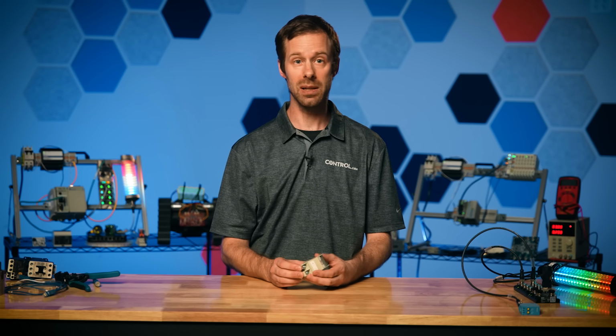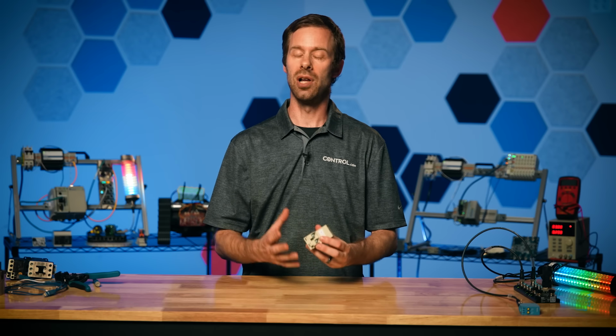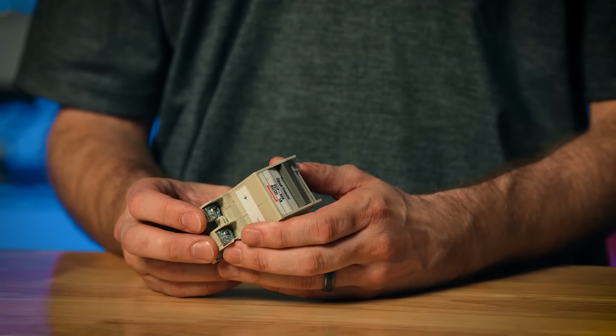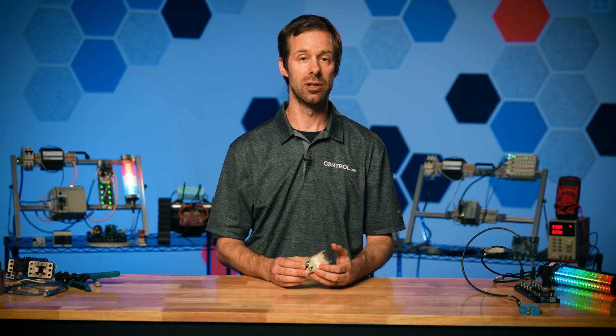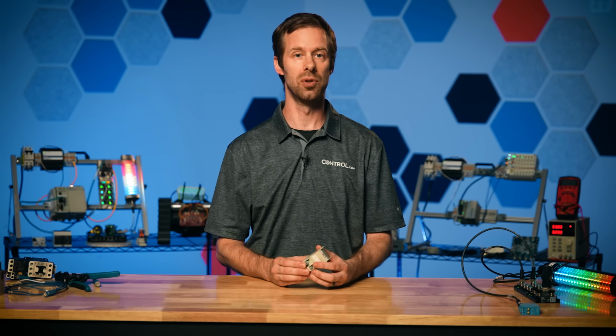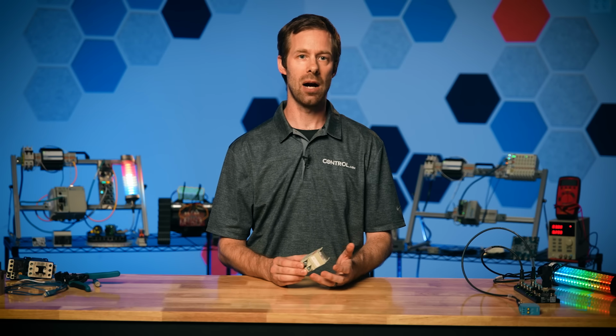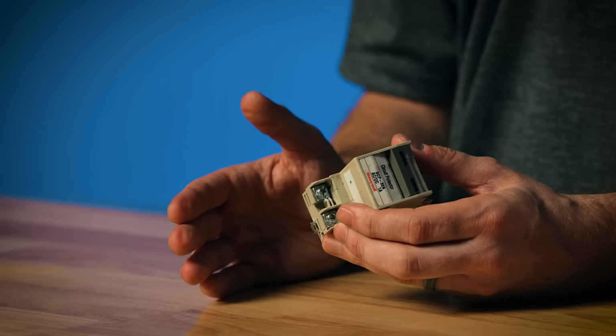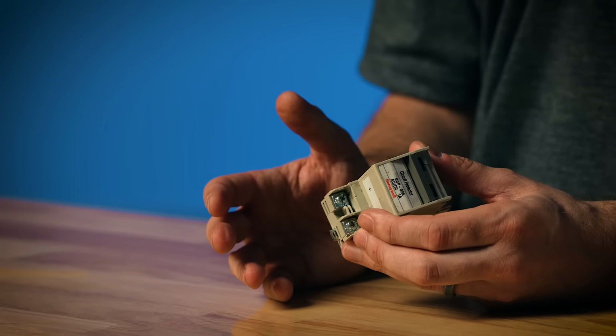Those inductive devices, especially motors, start up but take a lot of current while they're starting. That means that while they might operate with only a certain number of amps, say 10 amps, while they're getting started, they might be expected to take 15, 20, or even higher numbers of amps. So if that circuit breaker tripped immediately when it saw 15 amps, it would trip every time the motor starts. So we have to understand breaker curves, and there's a lot of them, and lots of tables to look up those ratings, but we have to understand how those work before we choose the right circuit breaker, especially for inductive devices and different load ratings for industrial motors.